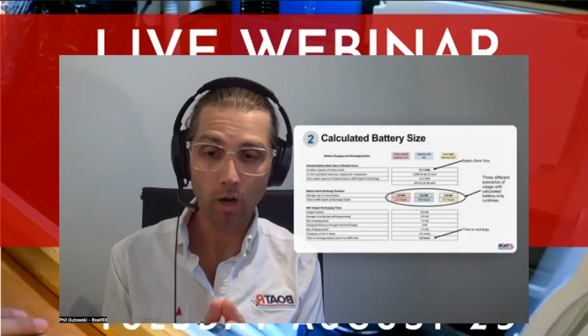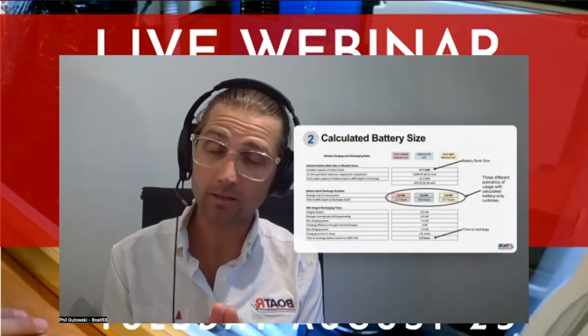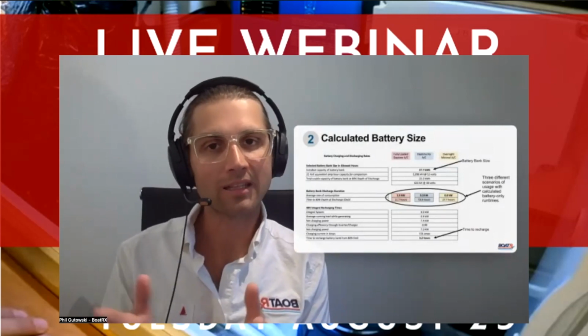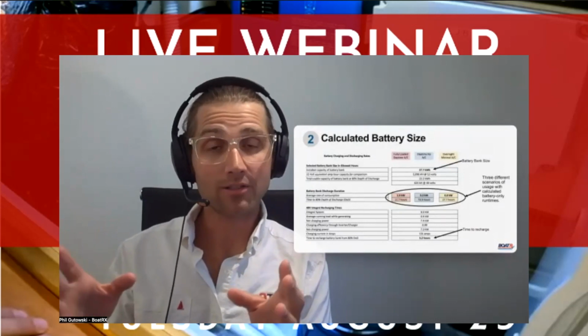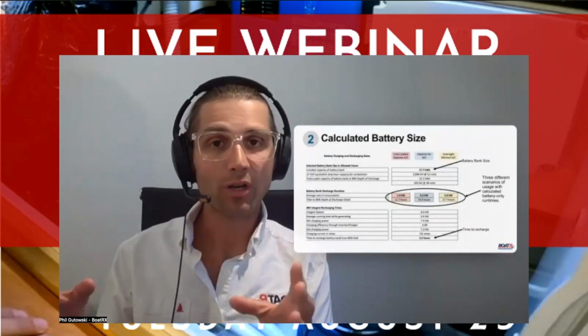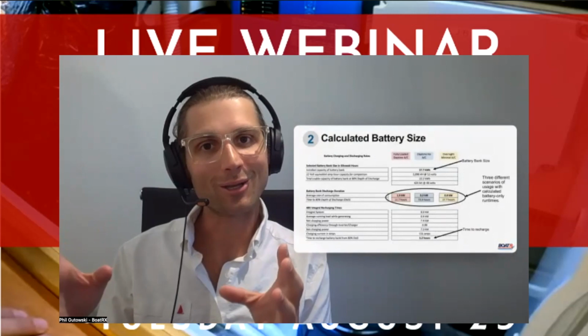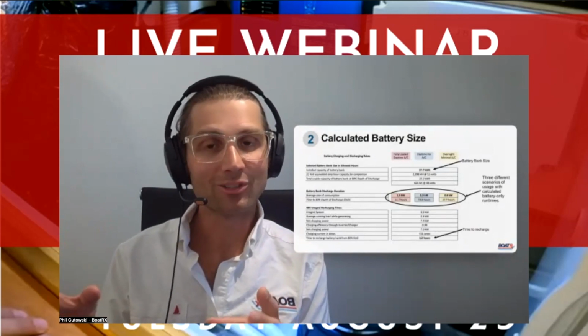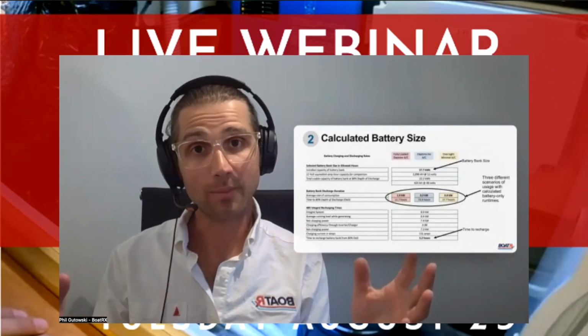In fact, we've run into this with clients who wanted big battery banks. They made the investment, and then I see their usage - they're not discharging much below 50 or 40% on a regular basis. With lithium batteries, you can use almost all of it, so that leaves 20 or 30% of their investment underutilized. That's why we don't want to oversize the battery bank.